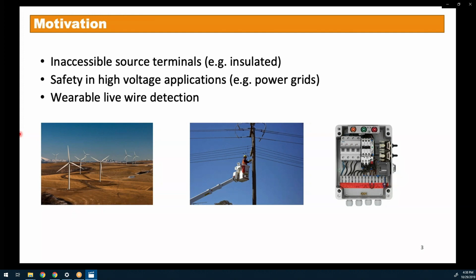So how does this work? We use an electrometer sensor, we'll talk about this later in the next slide, to measure the electric potential. The electric potential at a fixed distance varies linearly with the source voltage. Now, if you start to move the device, i.e. change the distance, you add a second variable because the electric potential also changes with distance. So at a fixed distance, you can calibrate the device for different source voltages and use it.